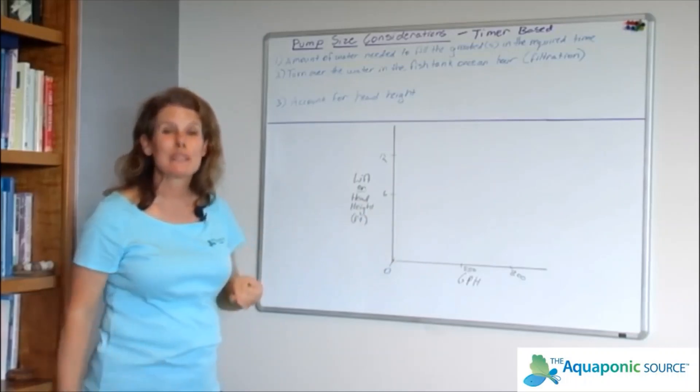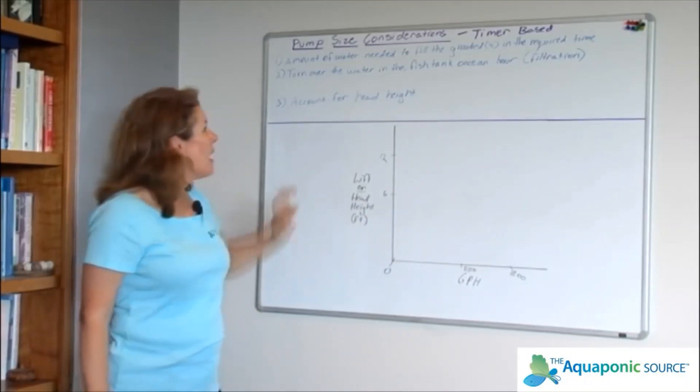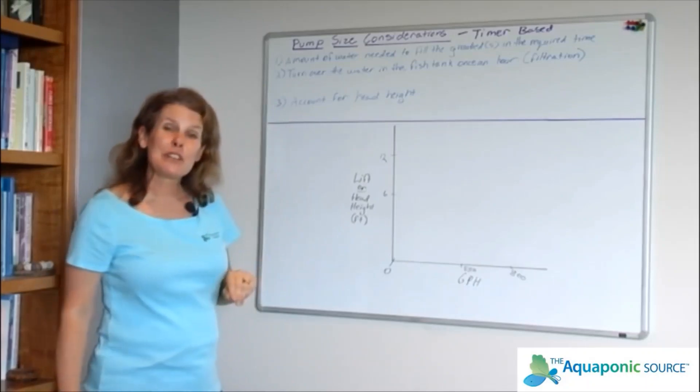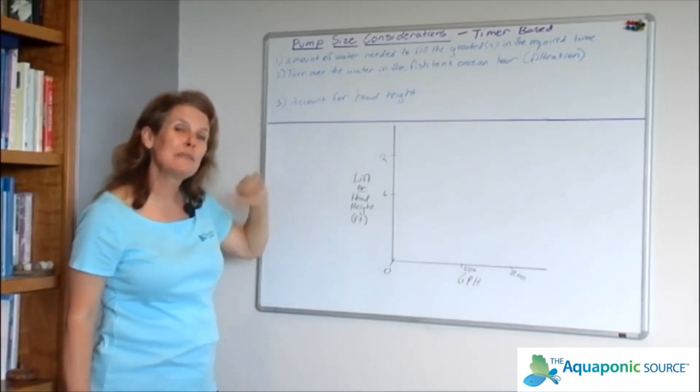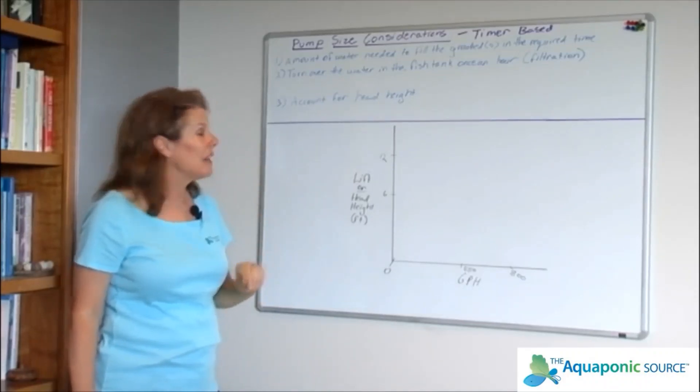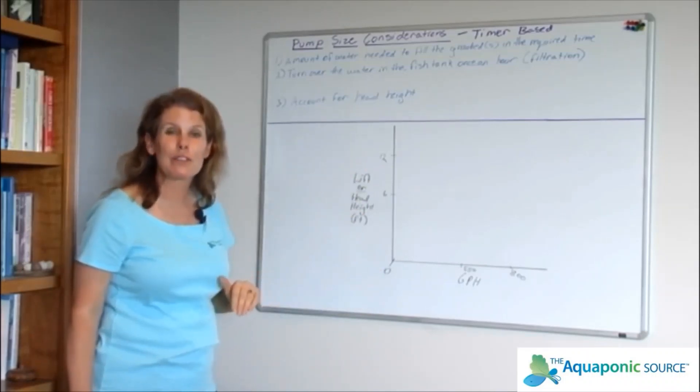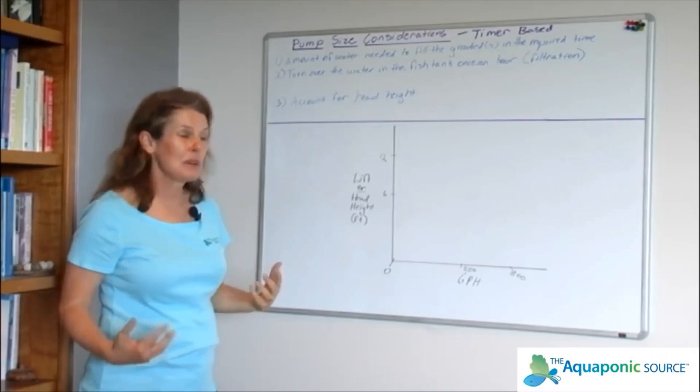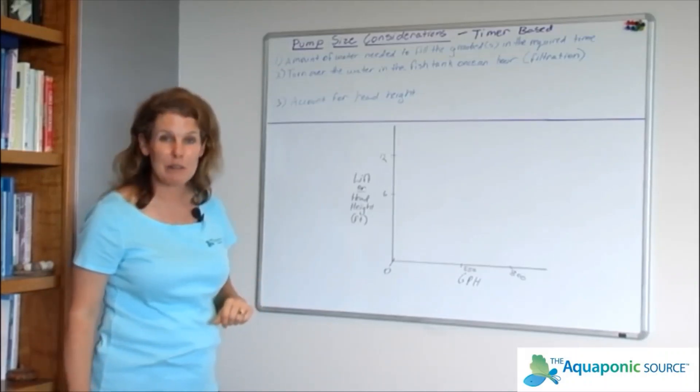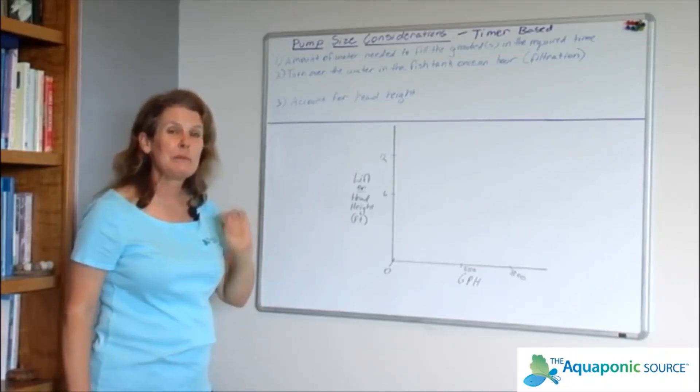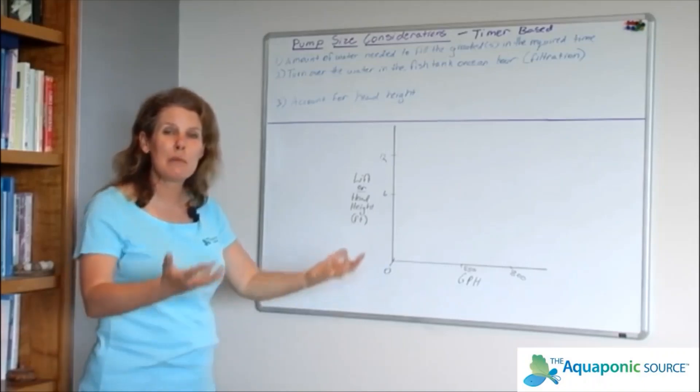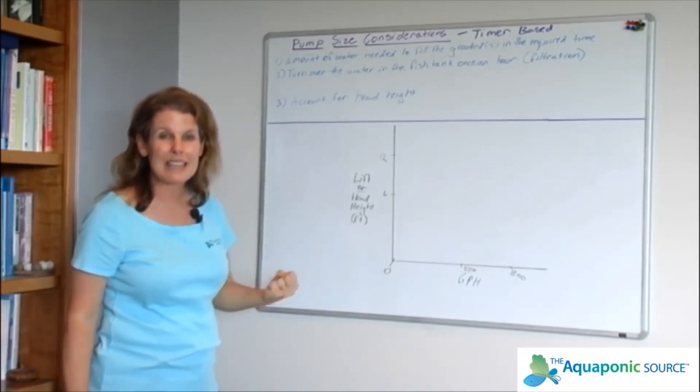The third consideration is something called head height, and this has to do with how far you're trying to lift that water against gravity to move the amount of water that you need to move. For example, if I have an 800 gallon per hour pump, that's only going to be moving 800 gallons at no lift. As soon as I've got to push that up against gravity, I'm going to start seeing a degradation of performance.